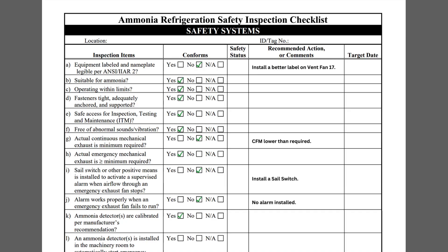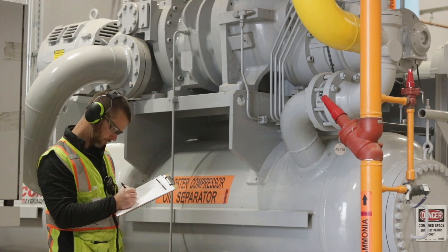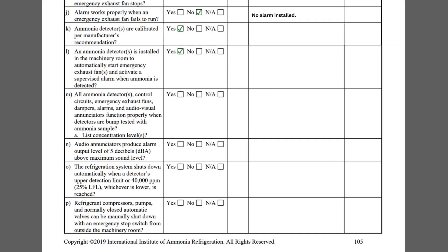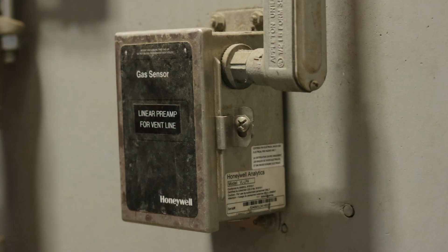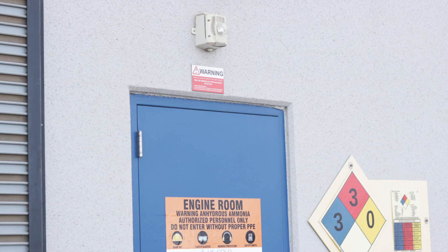Item K asks if the ammonia detectors have been calibrated per the manufacturer's recommendation. To know if the detectors have been calibrated at a proper frequency, you will need to access the facility's inspection, testing, and maintenance documentation. Checklist Item L requires the inspector to determine if the ammonia detectors are interlocked with the machinery room ventilation system and other supervised alarms. This was successfully verified and marked Yes.